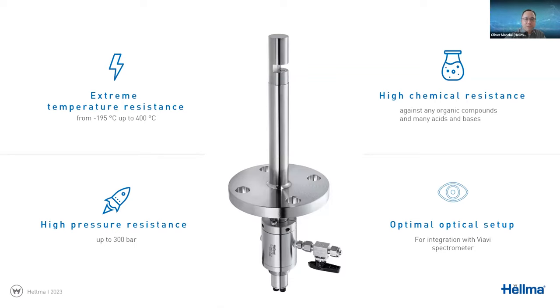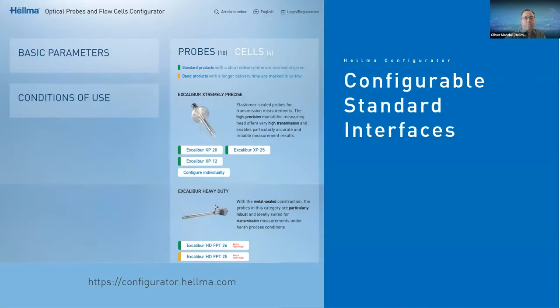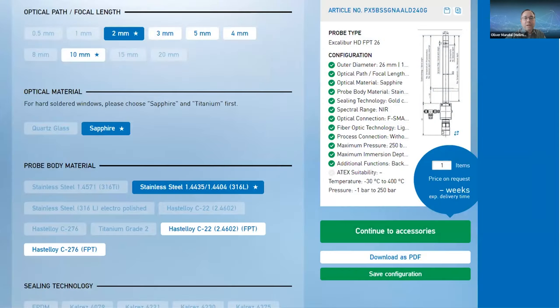The entire probe is purged with nitrogen — done once in production. When in use you don't have to care about it anymore. It maintains a slight overpressure that prevents moisture from affecting your spectrum and provides a second barrier, so if the probe front is damaged in production, chemicals cannot escape. If you want to explore the different options available, you can visit the Hellma online configurator for the Excalibur HD FPT, where you can find all technical information and configure path lengths, materials — stainless steel to Hastelloy — and process connections.